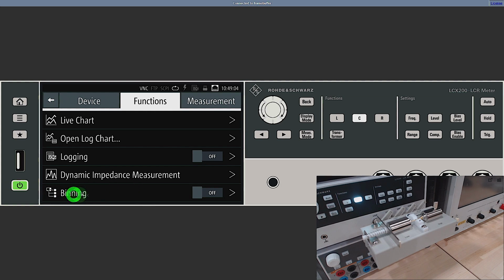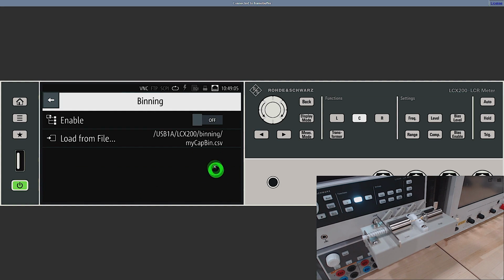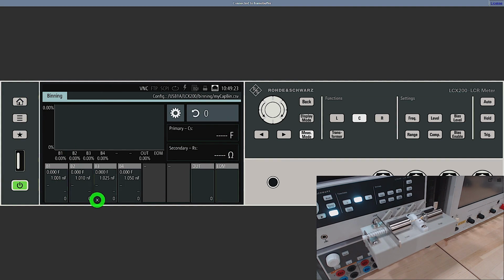Now to get to the binning function, we just go through this last item here in the menu, and you have to write a small text file, which you can put into the unit, which defines the different binning parameters in terms of percentage or absolute value. It's pretty easy to write, but you cannot define it natively on the screen. You have to load it from a USB, for example. Once you enable that, and then you go back over here, we get the binning menu. I have defined these capacitors in several different bins, 0.1%, 1%, 2.5%, and 5%. Now, if any capacitor I measure is above this value in bin 4, it's basically a reject because it's above the tolerance of the capacitor, and there is a bin here for that as well.